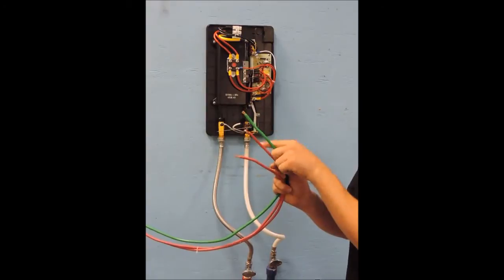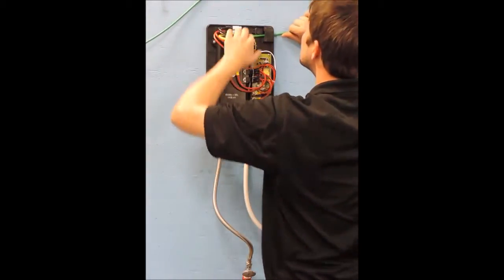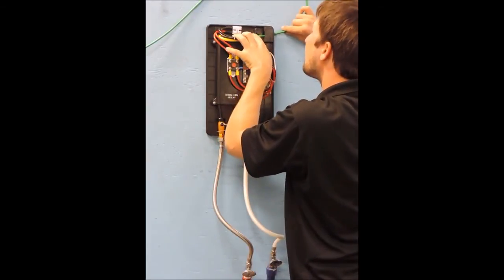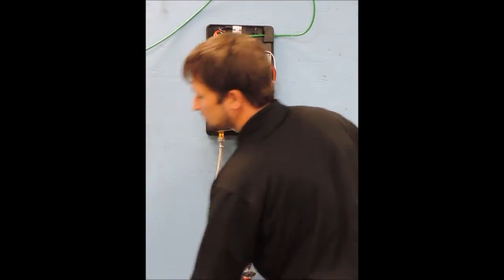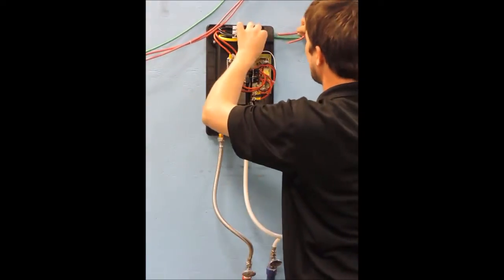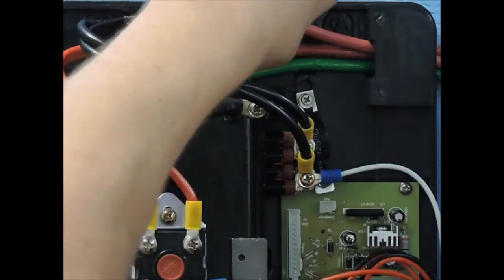Your power wires and ground will come into the unit from the upper right hand side of the back panel. The factory recommendation is 6 gauge wire for supplying power from the 60 amp breaker and for the ground wire. Run that ground wire from the opposite spot of the terminal block from the green and yellow wire. It may be labeled as E. Run that all the way to the ground bar of the breaker panel.